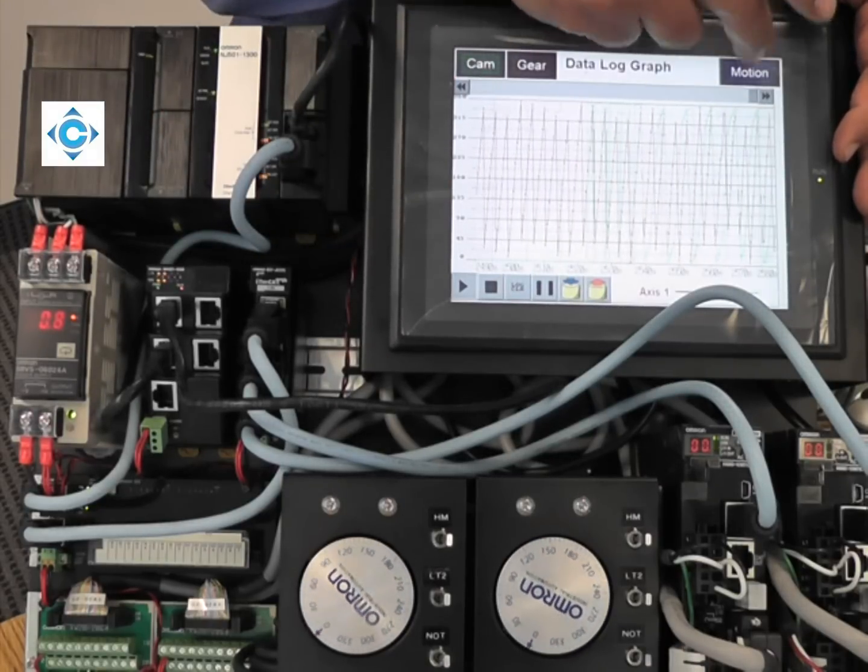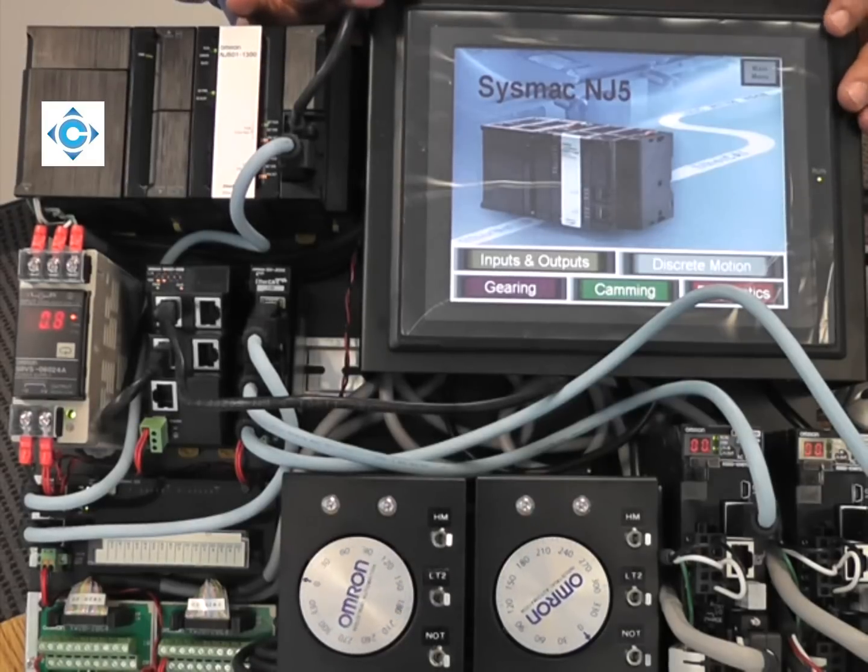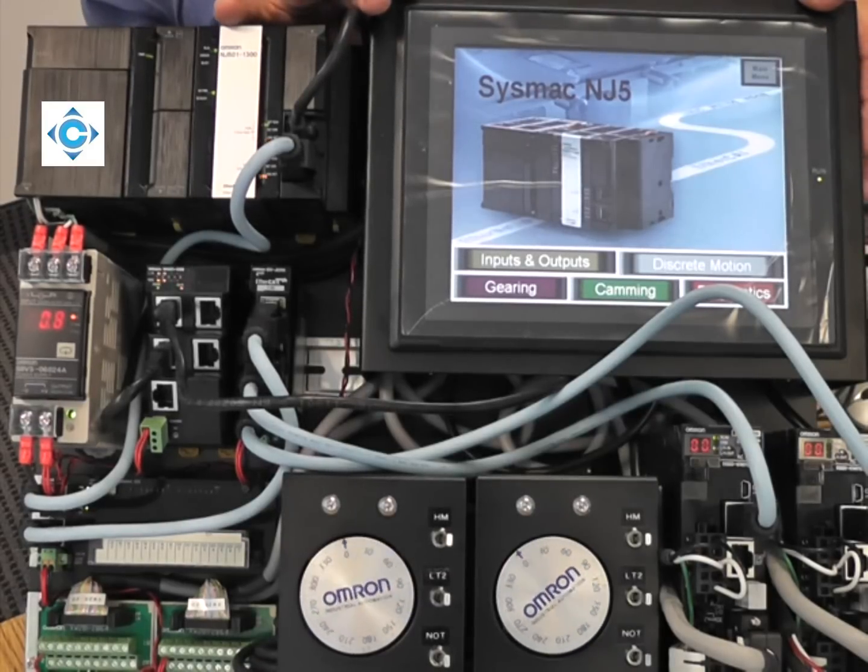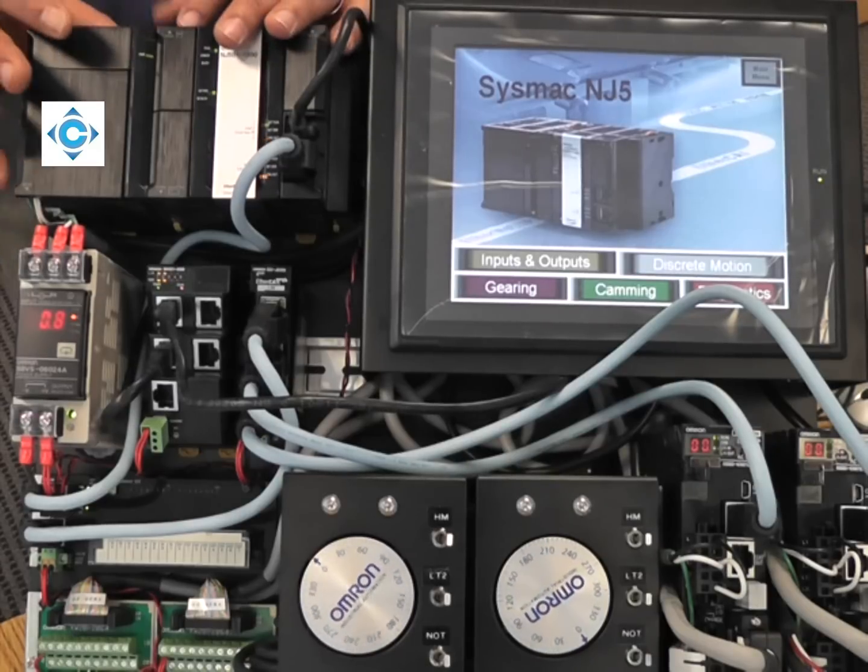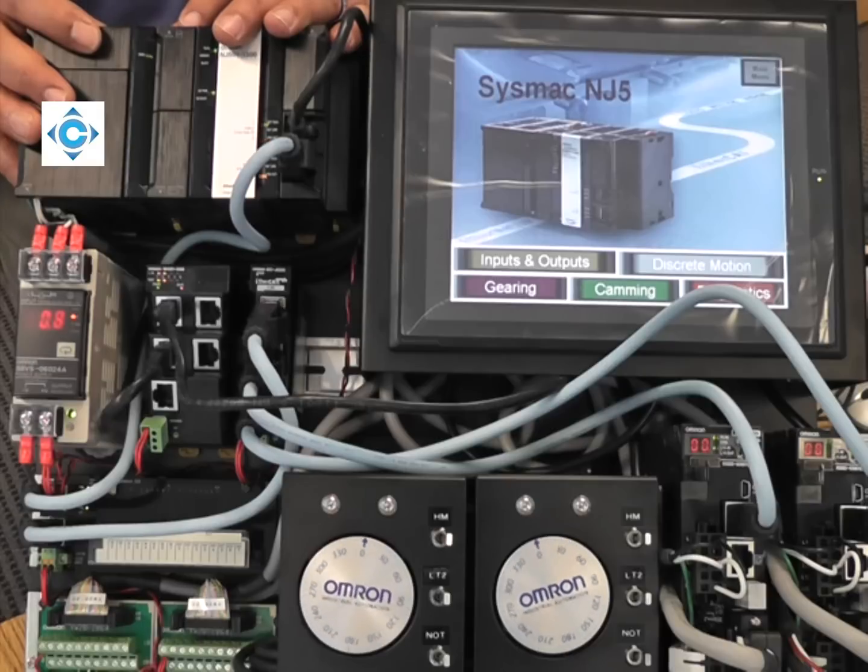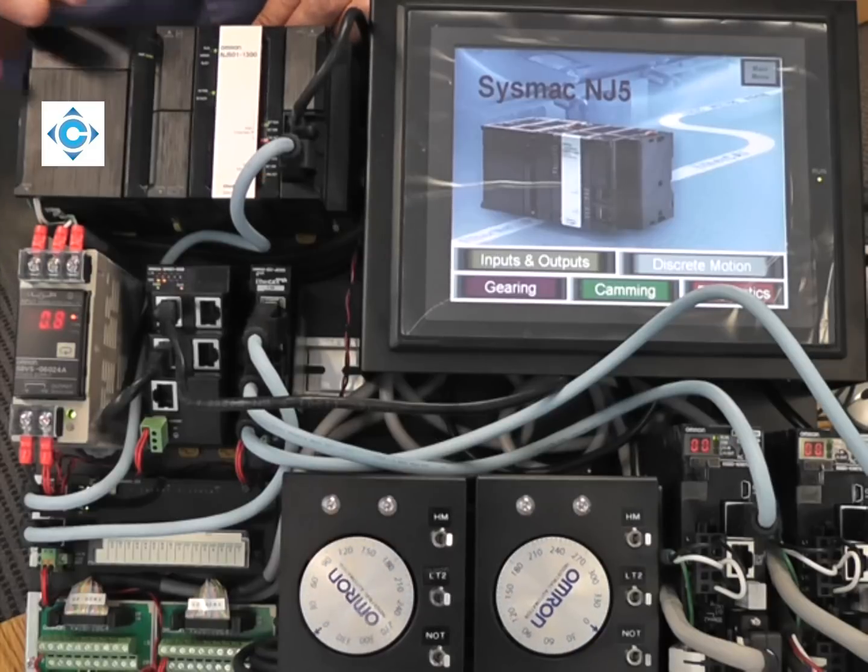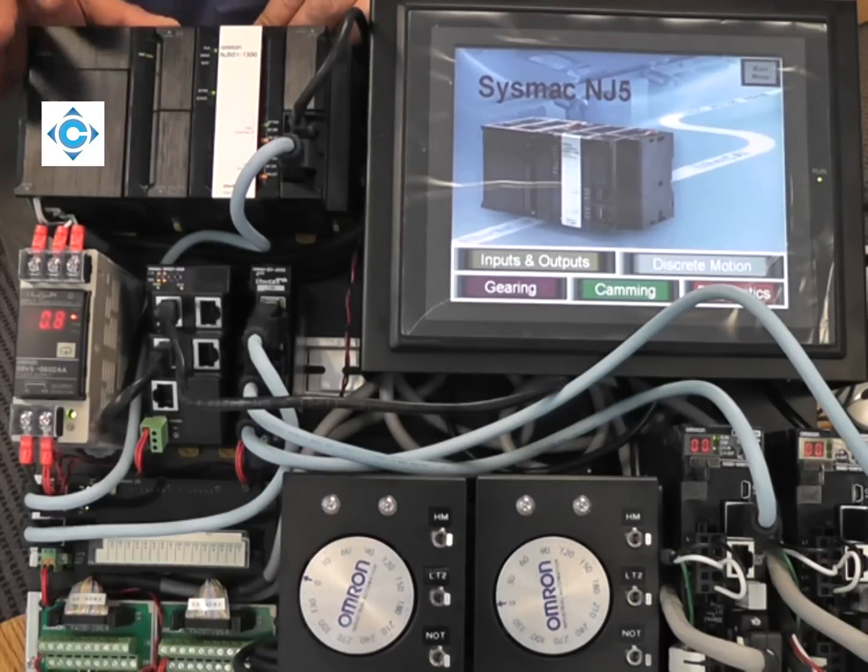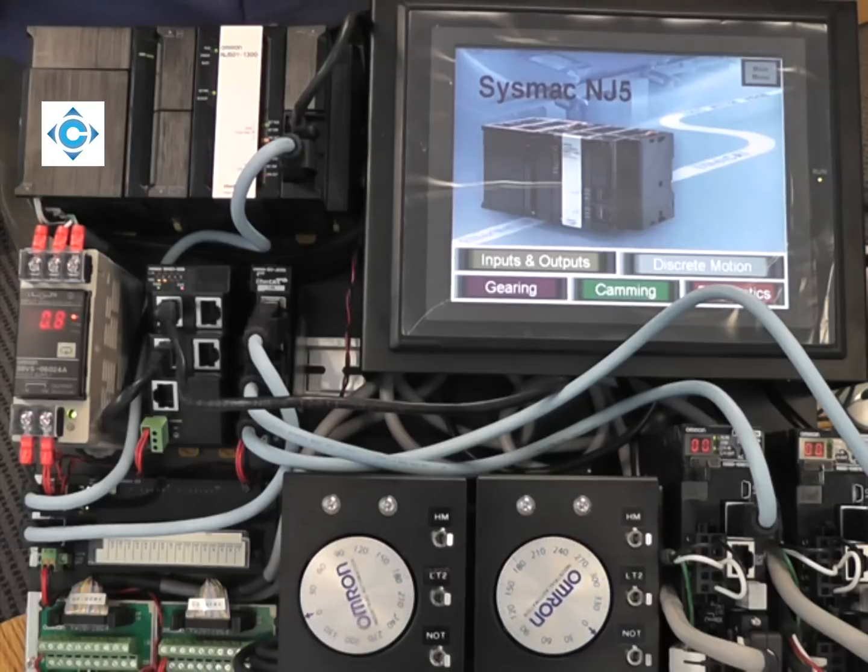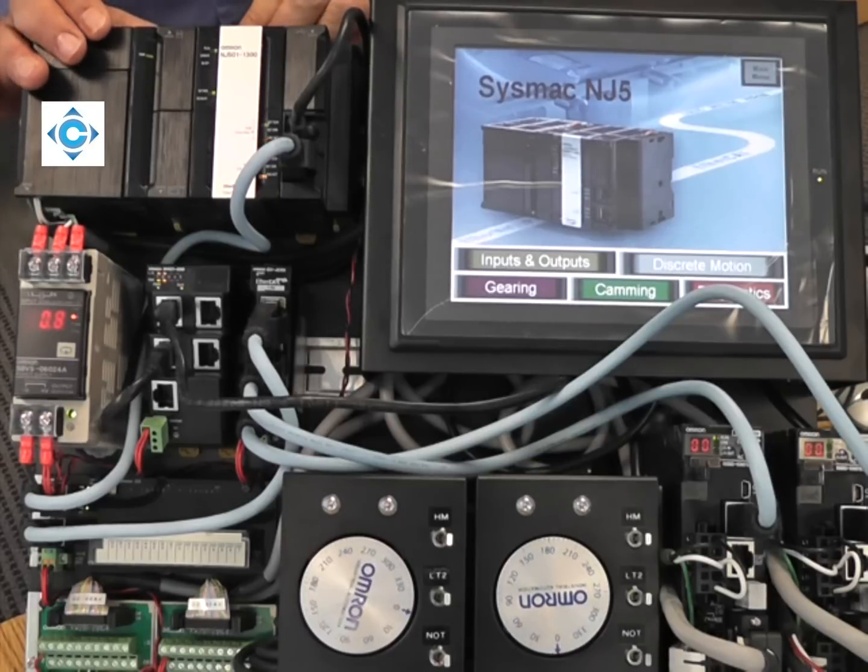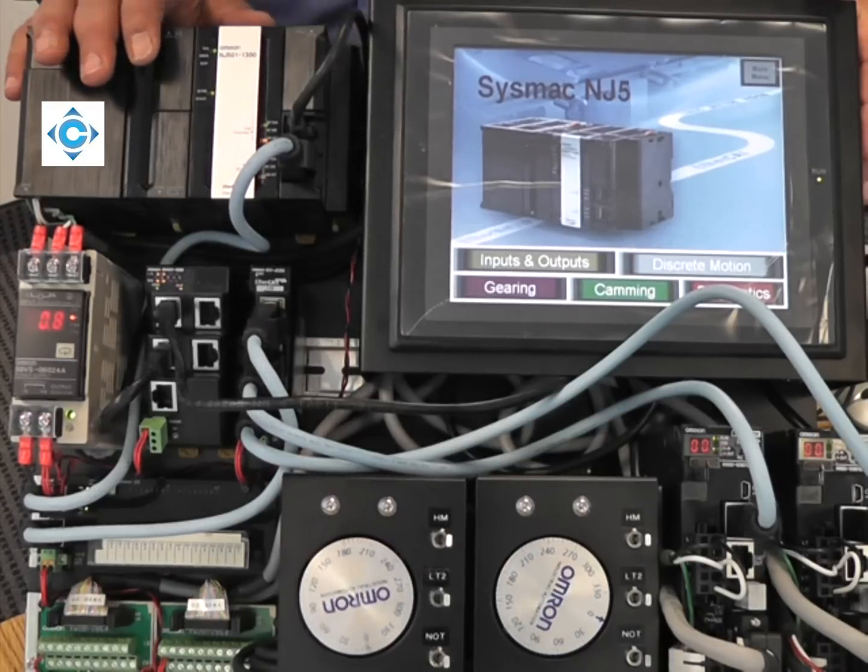The one I want to show next: our NS starting at version 8.5 has a built-in troubleshooting tool. Because NJ has centralized error reporting and event handling, it will record any fault on any node or any operation. Basically, the NJ has four built-in processes: one doing the motion engine, one doing the EtherCAT, one doing the Ethernet IP and one what we refer to as the PLC.